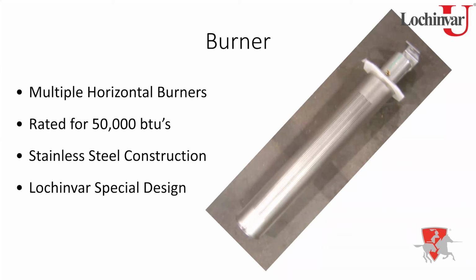So let me give you a little information about how to service these burners. When you're ready to do your annual, so once a year, I need the burners pulled, cleaned out, and I'm about to tell you how. I need that heat exchanger cleaned up like we discussed earlier in the presentation. So that Venturi baffle is exactly why I can't just blow air through this burner when I take it out to clean it. That baffle inside, I've got to have some type of fluid coming in contact with it, so that way I know 100%, hey, its ports are clean, I'm good to go. And water molecules are larger, so that's just going to clean it a little bit more, right? So that's what I need done once a year.